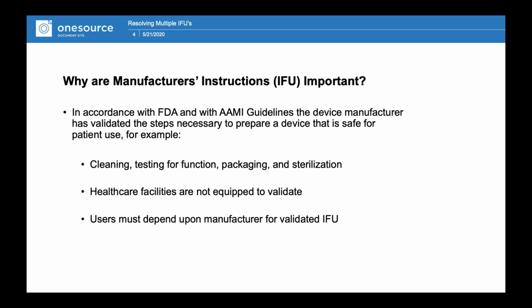But it's very important just to note, like I mentioned, some devices have to be taken apart for cleaning. Some devices remain apart on the assembly side, and then it's up to the operating room to potentially put it back together, and then vice versa. There's some devices that come apart for cleaning, they get put back together on assembly, and then it's sterilized the way that the IFU instructs us to.